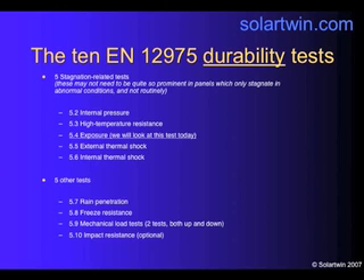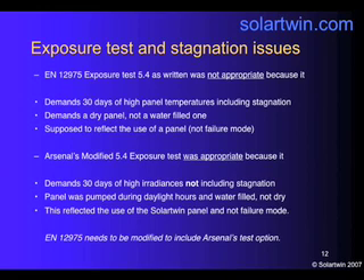Of the five that are related to stagnation, we're going to look at exposure test 5.4. It's not appropriate for Solartwin because of the continuous pumping nature of our system. Test 5.4 demands 30 days of high panel temperatures, including stagnation, using a dry panel and not a water-filled one, and it's supposed to reflect the use of the panel, not a failure mode. So Arsenal modified the exposure test to make it appropriate to Solartwin — still giving 30 days of high irradiances, but not including stagnation, by pumping the panel during daylight hours and keeping it water-filled but not dry — because this reflected the use of the Solartwin panel in normal use, not a failure mode.